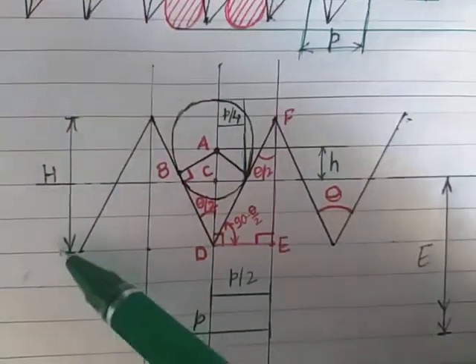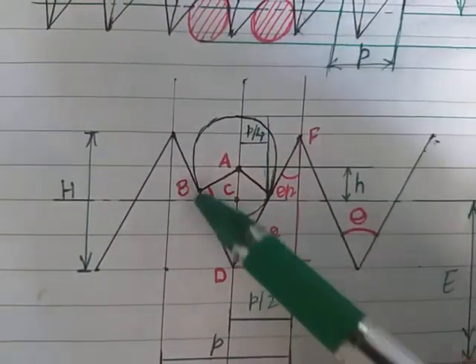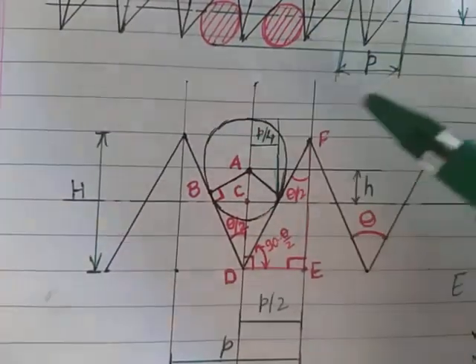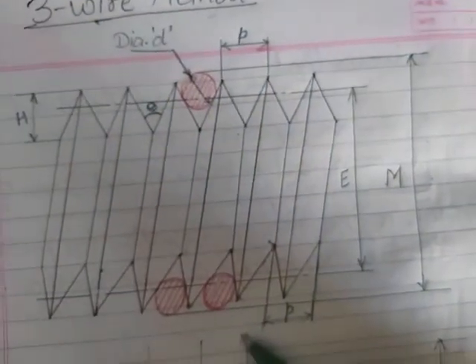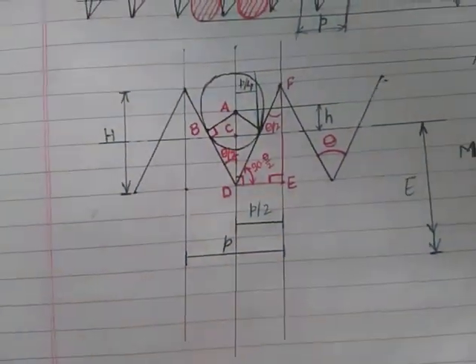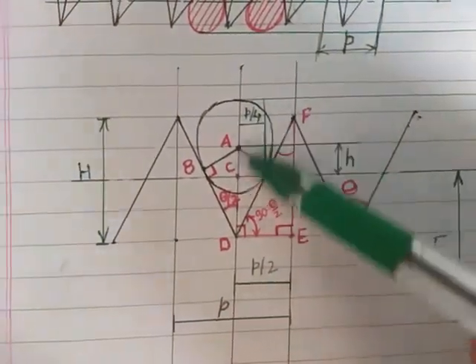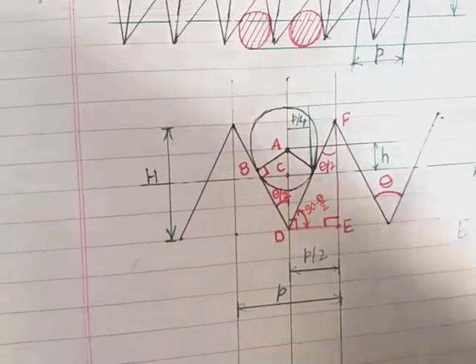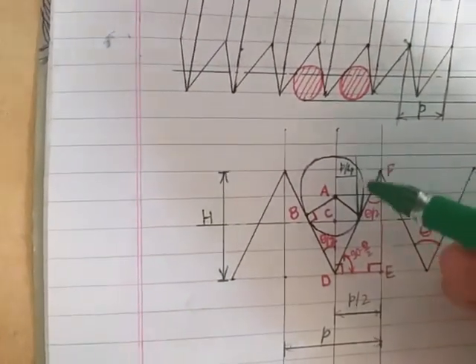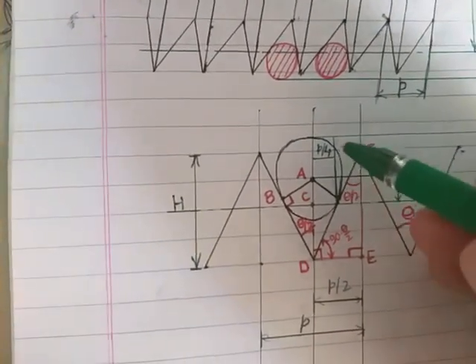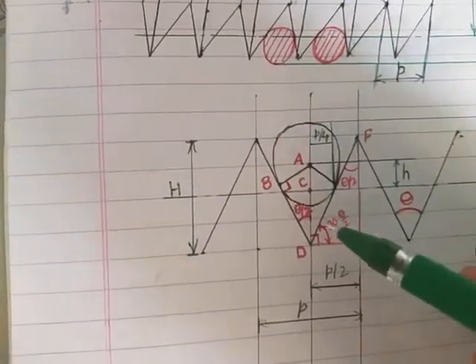Zooming into the main diagram: over the thread profile we have inserted this wire of diameter small d, so the radius will be small r. From one point to the next, this distance is your pitch p — the distance between two consecutive threads at the same point. This pitch is divided into two parts at the center: this is p by 2, half of the pitch. At the point of effective diameter, this distance will be your p by 4.